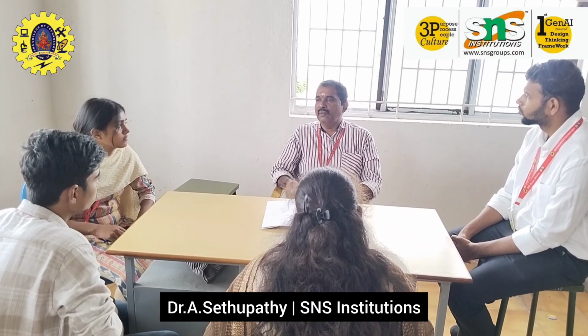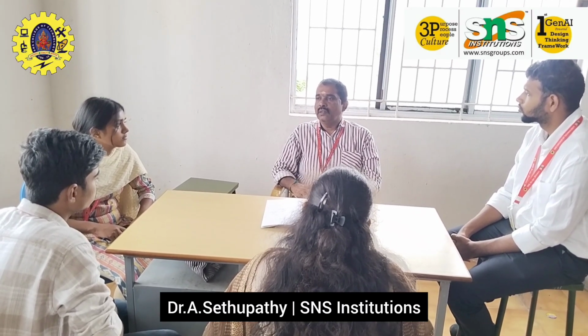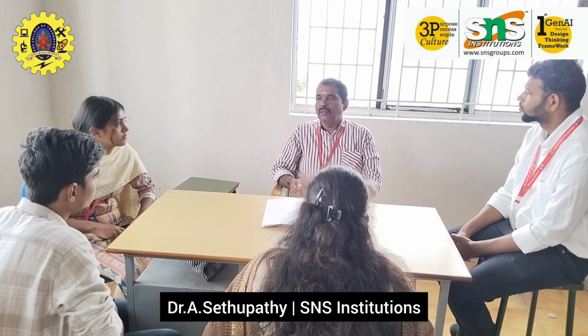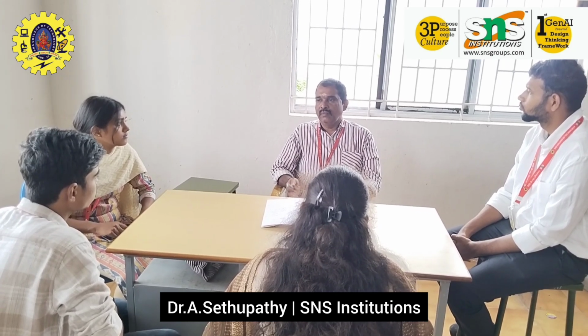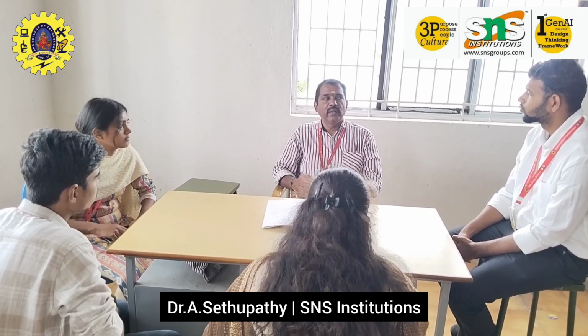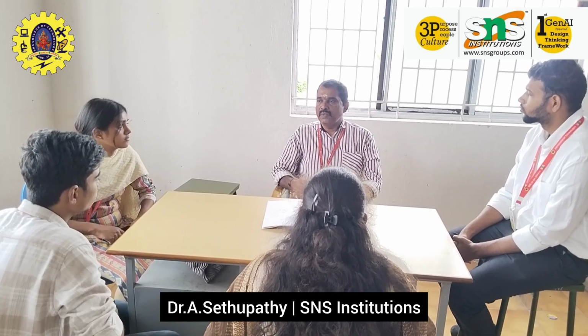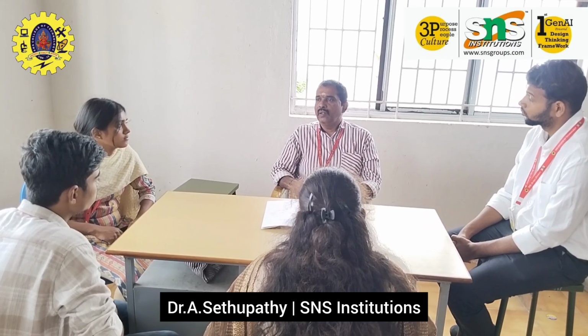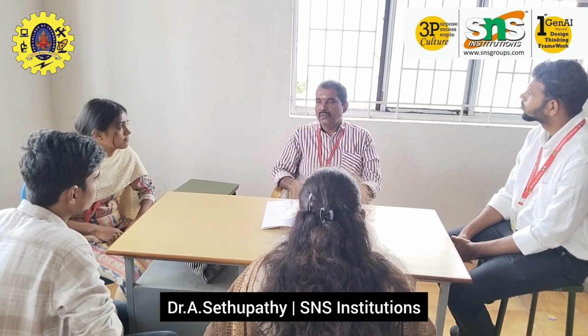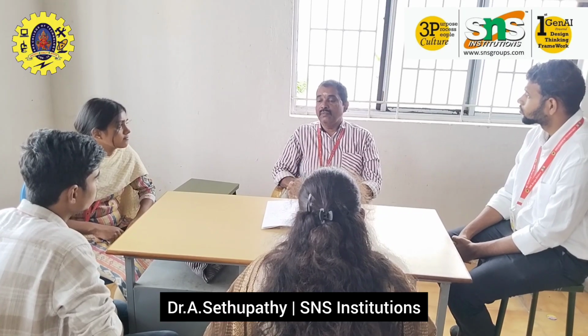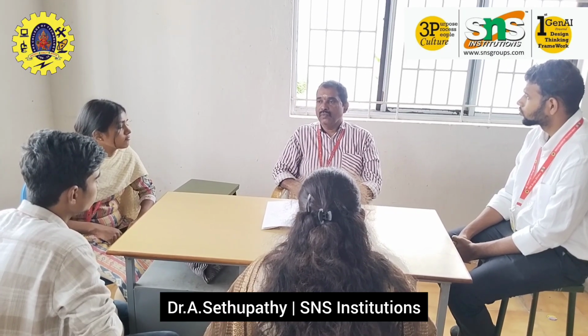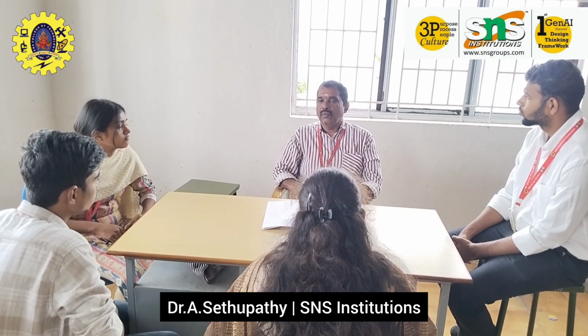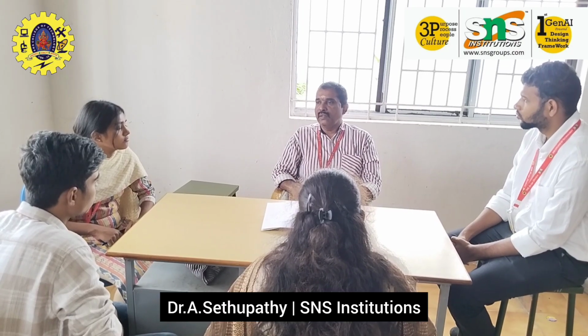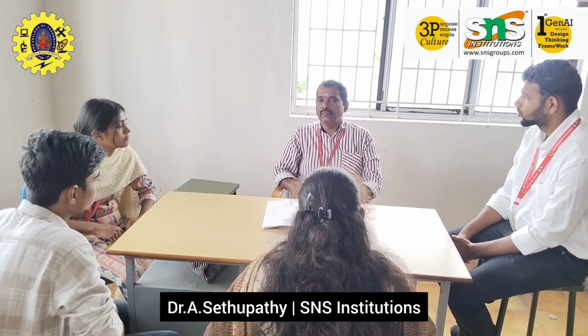Sometimes the impeller will be worn out and the efficiency of the water discharge is very low, and sometimes it is very noisy, and sometimes the motor runs slow. So the RPM is very important for the centrifugal pump. I hope everyone understands what a centrifugal pump is and where we are using it. Thank you.